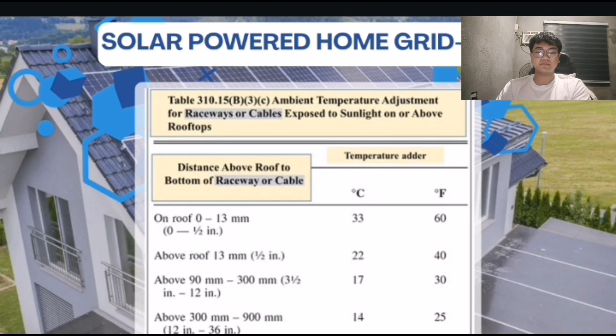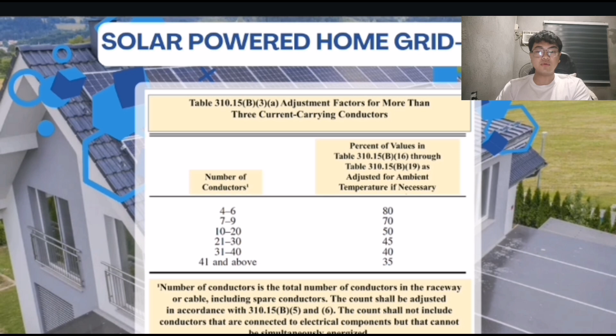The next table is 310.15(B)(3)(a), which is standard from the National Electrical Code. This table specifies adjustment factors, also known as derating factors, for electrical conductors. When you bundle multiple current carrying wires together in a single conduit or cable, they generate heat. If there are too many, that heat can damage the insulation. To prevent this, the ampacity of the wire must be reduced. This table tells us how much to reduce the power in each wire as you add more wires to the bundle. It ensures that no matter how many wires are packed together, they stay cool enough to operate safely.